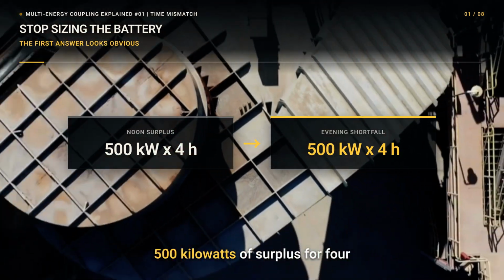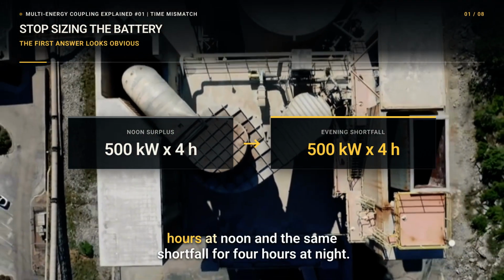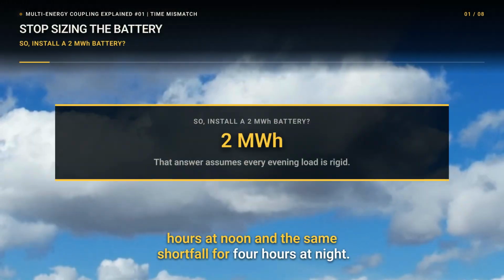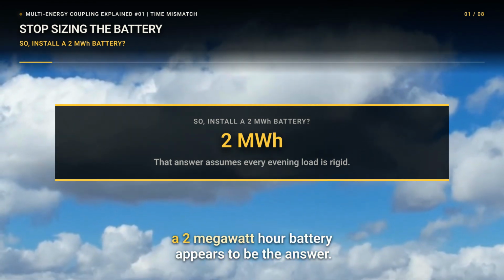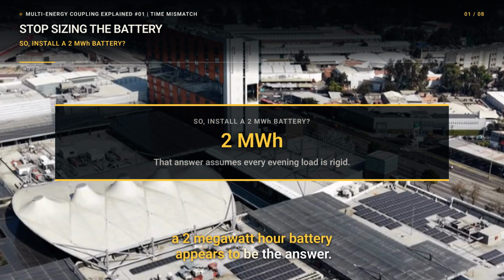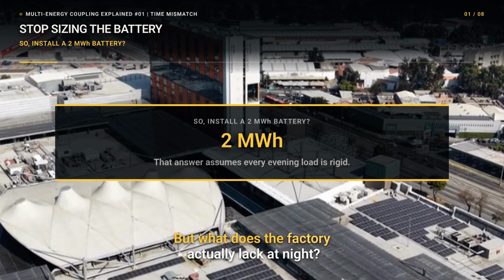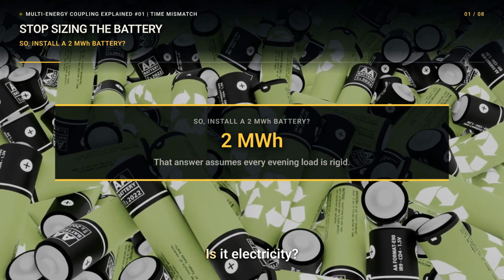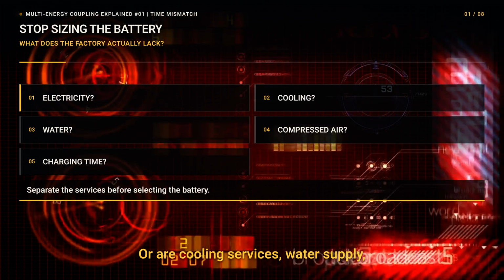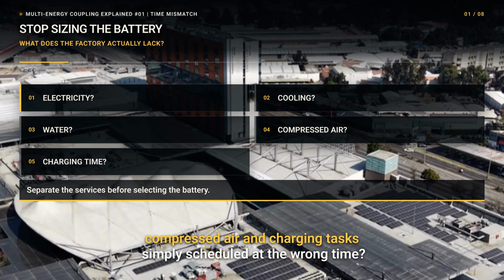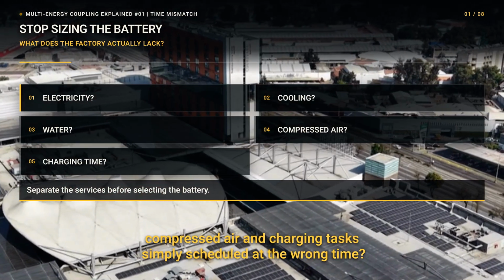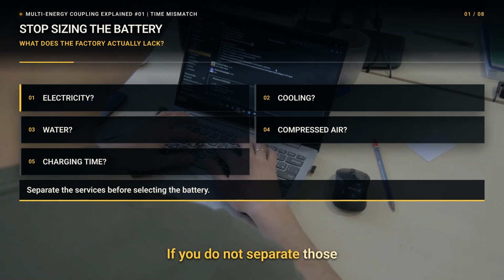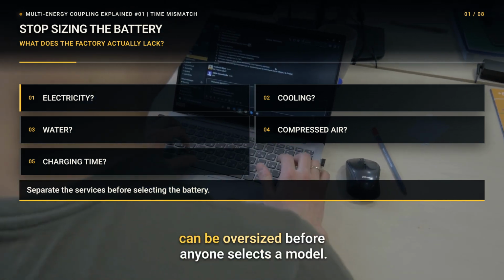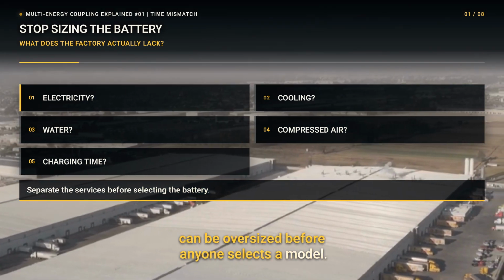An obvious answer seems simple: 500 kilowatts of surplus for 4 hours at noon, and the same shortfall for 4 hours at night. A 2-megawatt-hour battery appears to be the answer. But what does the factory actually lack at night? Is it electricity? Or are cooling services, water supply, compressed air, and charging tasks simply scheduled at the wrong time? If you do not separate those questions, the battery can be oversized before anyone selects a model.